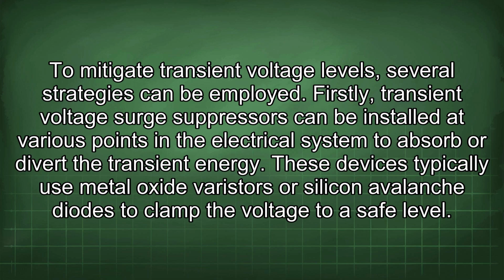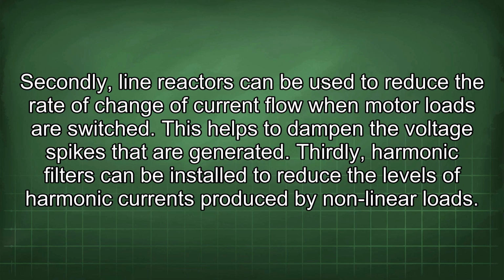Firstly, transient voltage surge suppressors can be installed at various points in the electrical system to absorb or divert the transient energy. These devices typically use metal oxide varistors or silicon avalanche diodes to clamp the voltage to a safe level. Secondly, line reactors can be used to reduce the rate of change of current flow when motor loads are switched. This helps to dampen the voltage spikes that are generated.